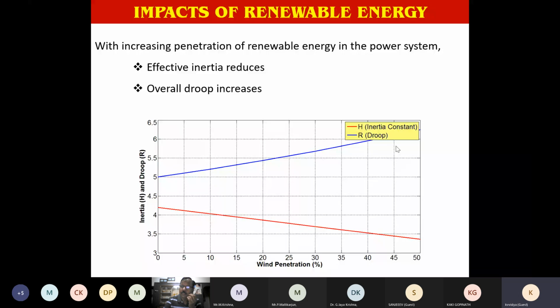Now, inertia means basically the stored kinetic energy. That will come down with an increase in renewable energy. So inertia will decrease, and there is another parameter that is called droop. Droop will increase. For faster response from a generating unit, droop should be lower. Lesser the droop, faster the response. But with the increasing share of renewables, droop will increase and inertia will decrease.